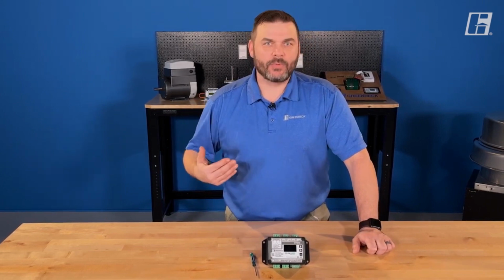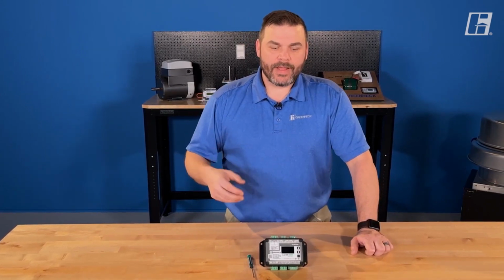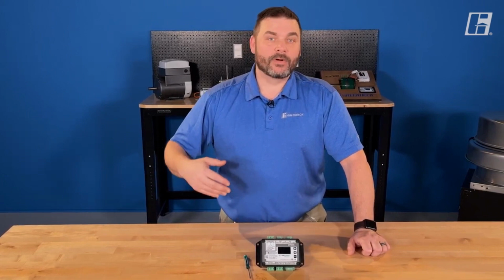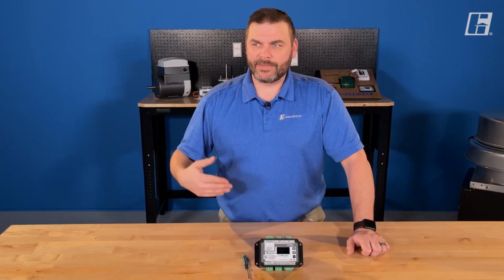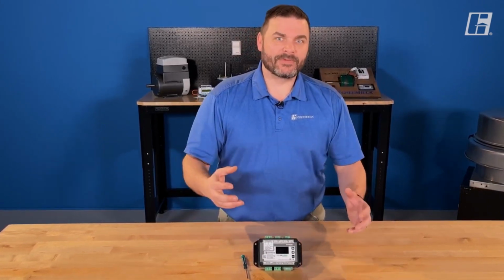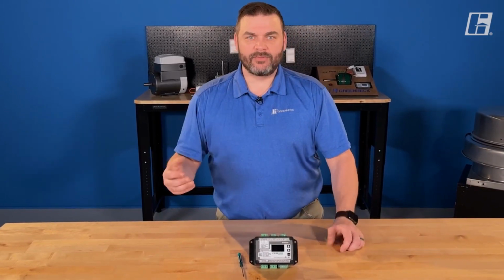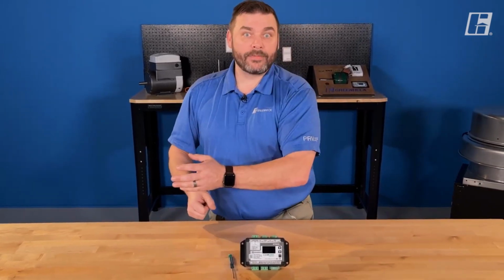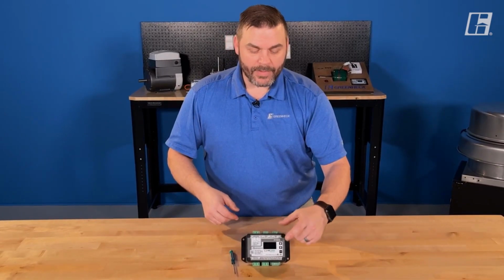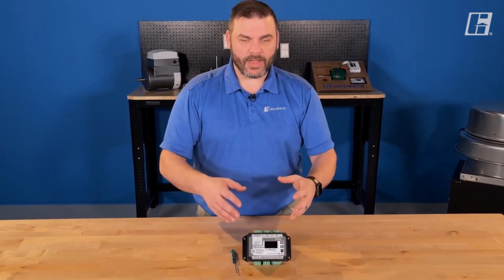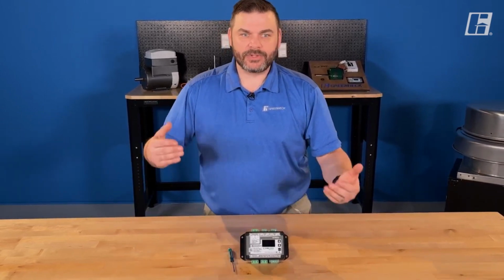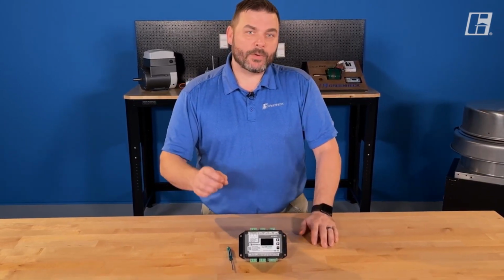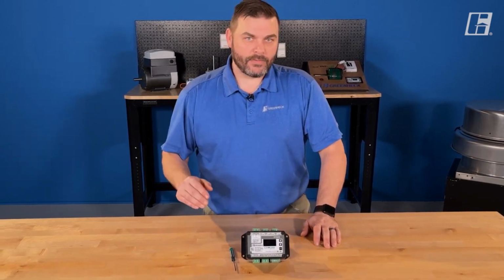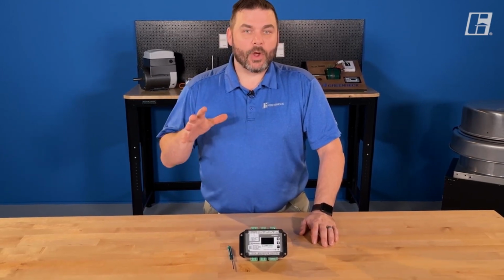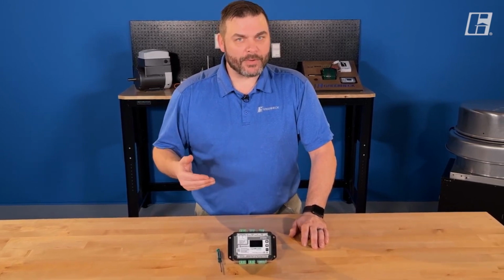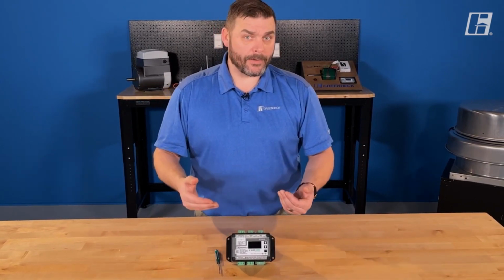And that gets us back to a life safety principle. If I'm hooked up to a fire alarm, or if I'm hooked up to a carbon monoxide, carbon dioxide type alarm system, I want to hit the second speed, whether it's full speed or off. I want to do that, and I don't want the ability for someone to change the state or another device to turn on and change what we've done. So that terminal, when enacted, takes precedence. You have to physically let go or remove voltage from that terminal, and it'll return back to its normal state.